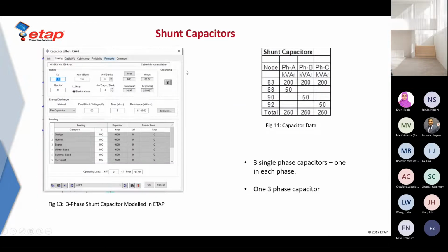Shunt capacitors. The system has in total 4 shunt capacitors, 3 of which are single phase, each servicing phase A, B, and C at 50 kVAr, and one 3-phase capacitor that serves 200 kVAr per phase at node 83. So here we have the capacitor editor and how it's been organized. So in total, this supplies about 600 kVAr.